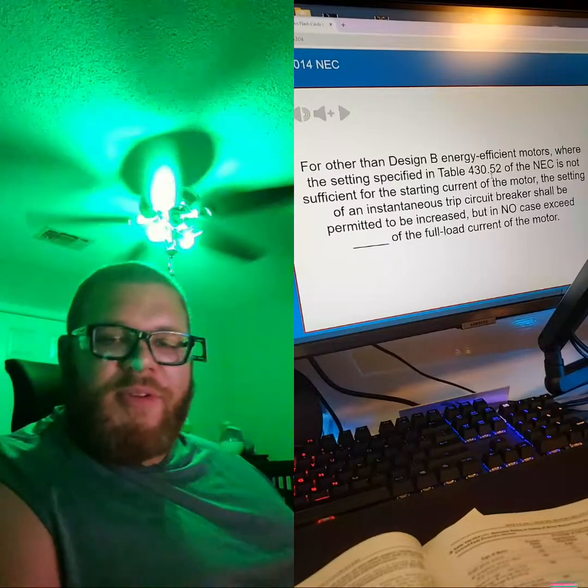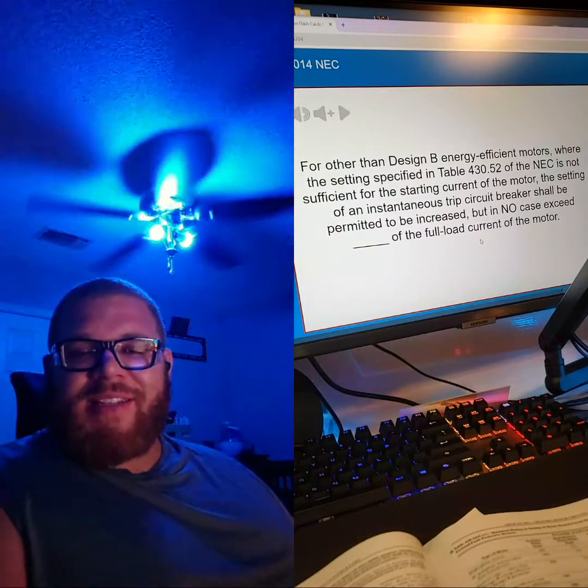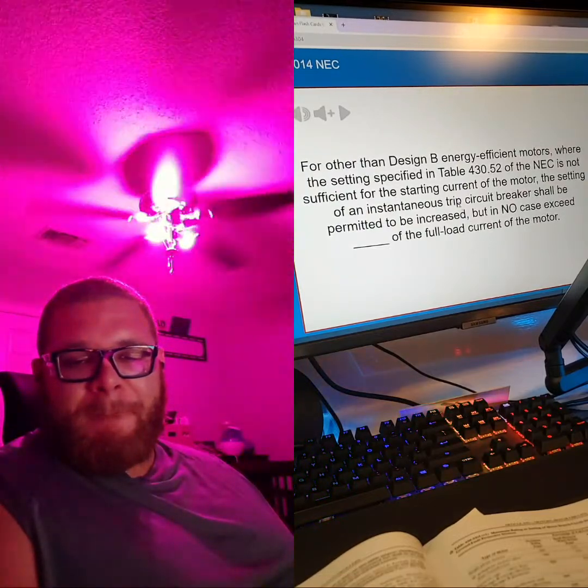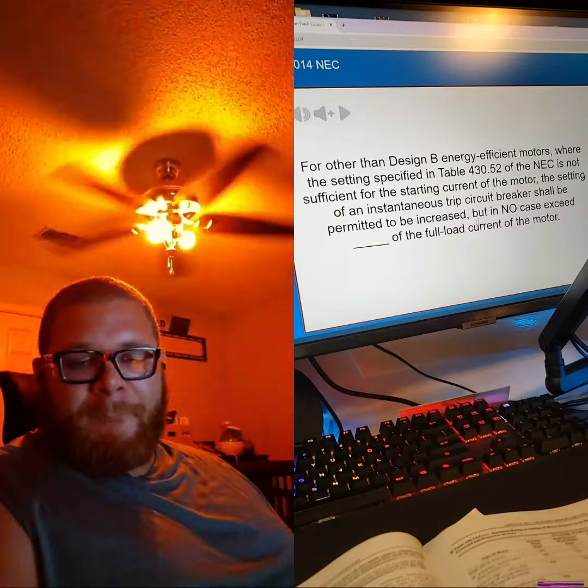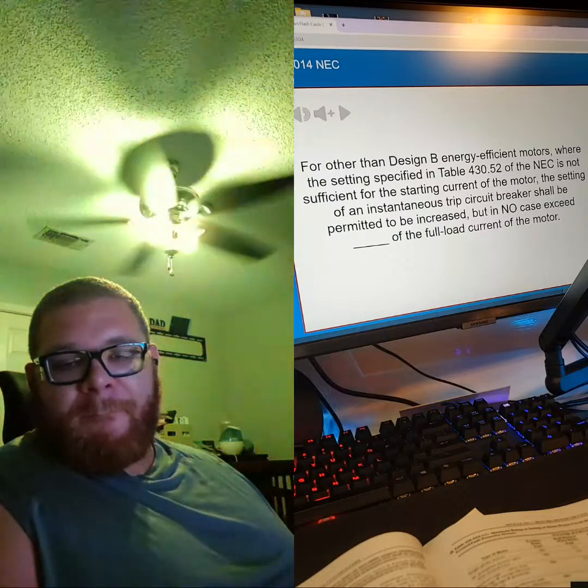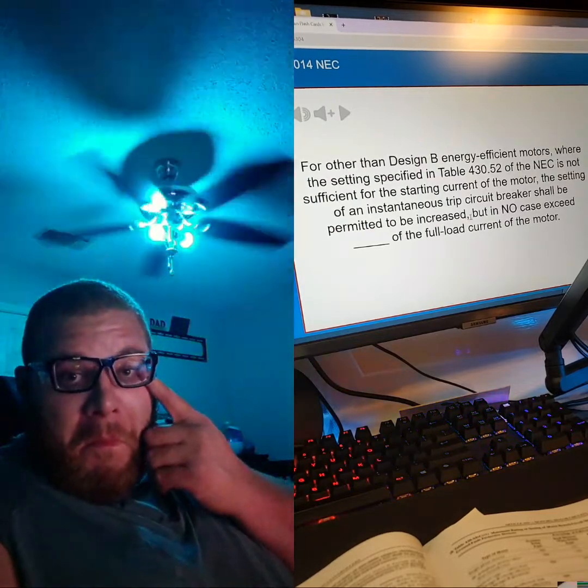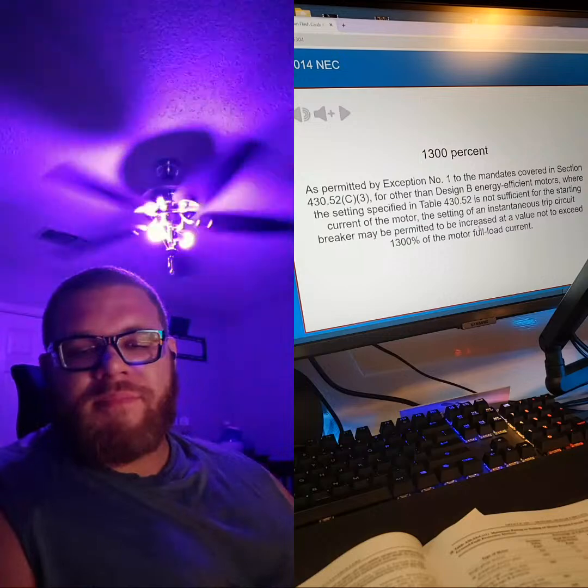So what's the answer? Let me guess before I click it. Your guess is 1100%, because that's what it says. I was originally going to go with 800, and then I saw the 1100. It's instantaneous trip, but in no case exceed. I'm going to go with 1100 because it says no case exceed, which should be the maximum. I feel like it's going to be 800 though. I've never actually seen a scenario where it's been more than 800, but let's see. It's 1300.